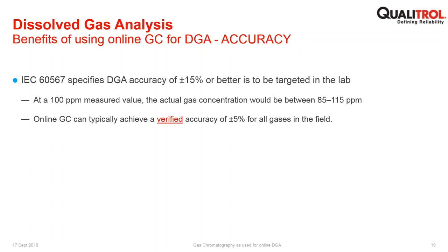Okay, just a couple of slides left. So the benefits of using online GC for DGA, the primary one is accuracy and certainty in that accuracy. So you're operating off a fixed calibration point that has been determined in the last number of days. And you're also operating in an isolated environment. So you have your own carrier gas. You're not influenced by external factors.